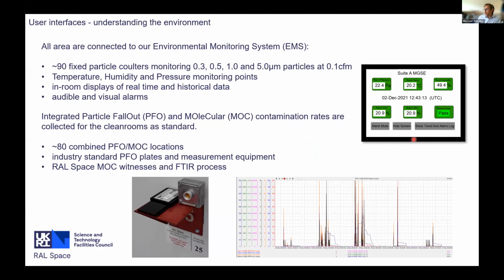As far as what we do in all of the rooms, the services are pretty much similar wherever you go in our facilities. We have about 90 deployed particle counters across the buildings. We monitor temperature, humidity, and pressure, and display that in the room on screens, with audible and visual alarms. We monitor particle fallout and molecular contamination, as you'd expect in clean rooms, and we have about 80 of these spread across the buildings.